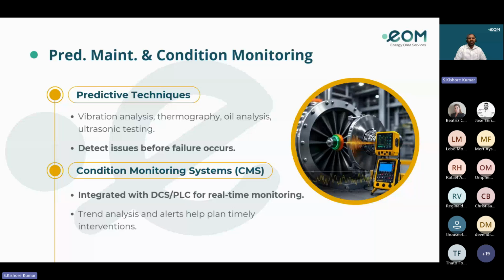Coming to predictive maintenance and condition monitoring. For predictive techniques like vibration analysis, we have to do the vibration analysis, and we also have to check whether all the vibration sensors are reading well, and do the inspection or calibration of the sensors. That is so important.